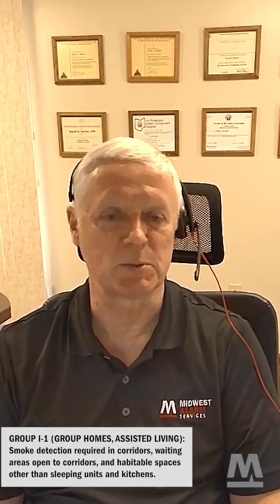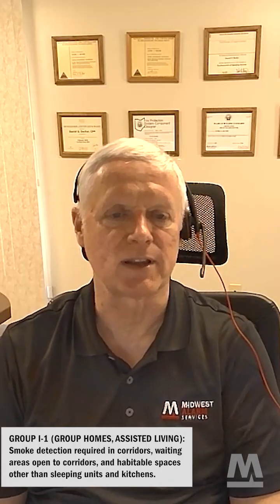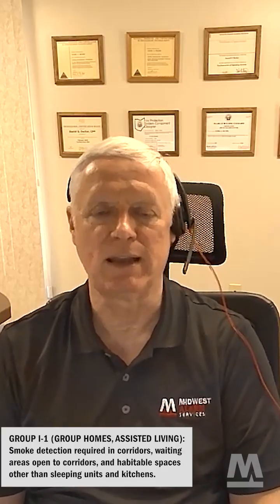Group I1 requirements, specific requirements for group homes and assisted living, are that smoke detection is required in corridors, any waiting areas that are open to a corridor, and habitable spaces other than sleeping units and kitchens. The exceptions are that smoke detection in the habitable spaces is not required in a fully sprinklered facility, and smoke detection is not required for exterior balconies, which kind of makes sense. It's a concern if a fire starts on an exterior balcony, but we don't put smoke detectors out there. Smoke alarms shall be installed on the ceiling and walls outside of each separate sleeping area and in each room used for sleeping purposes and on each story within a dwelling unit. And that's per section 907.2.11, which we'll cover eventually, but that deals with the single station smoke alarms.